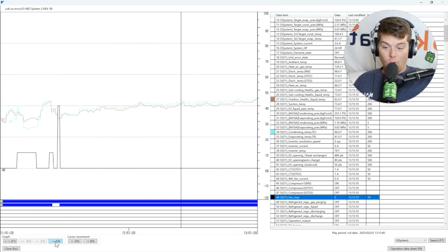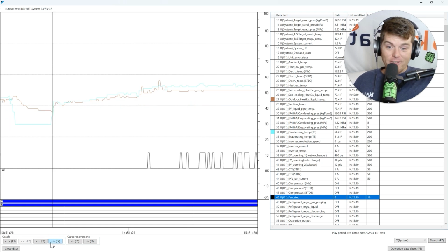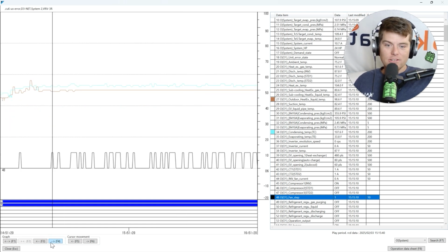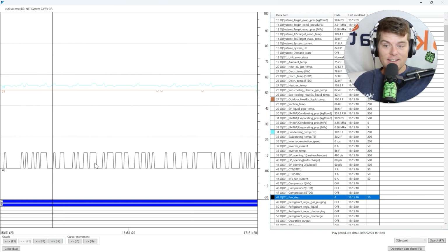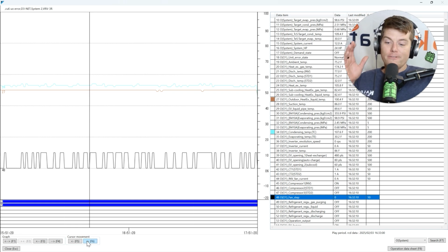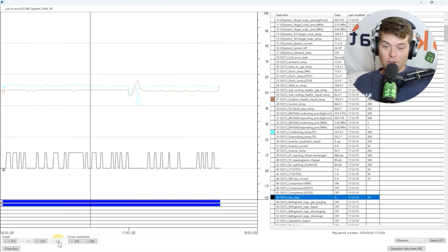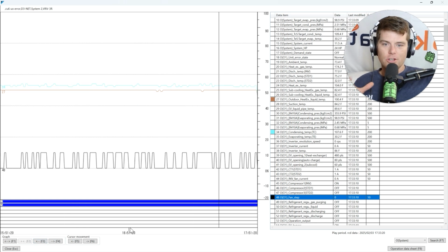And notice that it's only when I get to the end of my data after 6 hours, not in the 26 minutes I told you don't do. It's only at the end of the data that I see it. Look at all this sporadic fan on, off, on, off. Fan speeds will also allow you to troubleshoot systems to determine if there was an issue. If you walk past the system and the fan is on, off, on, off, and the other module is not running and it's the middle of summer and you know that system should be working its butt off, it should be a red flag in your mind that, hey, I'm here to look at that error code, but that system is low on charge.